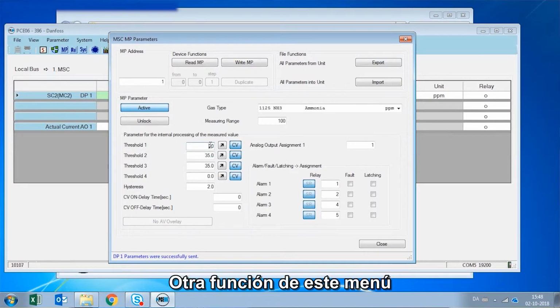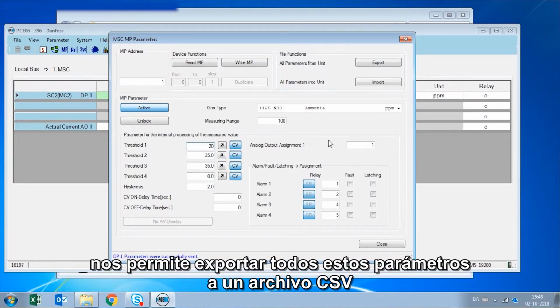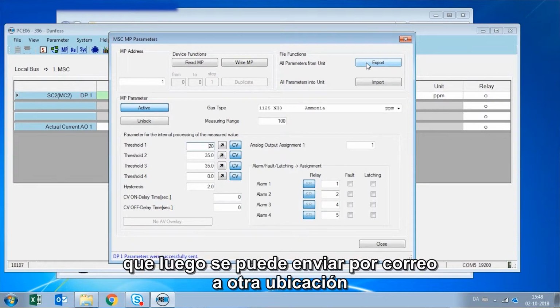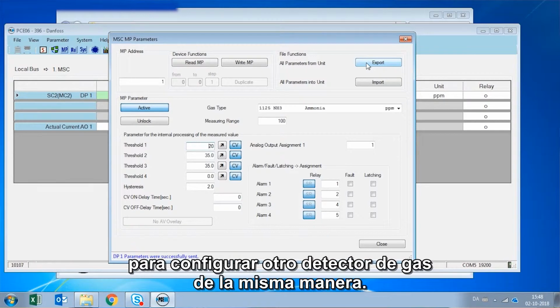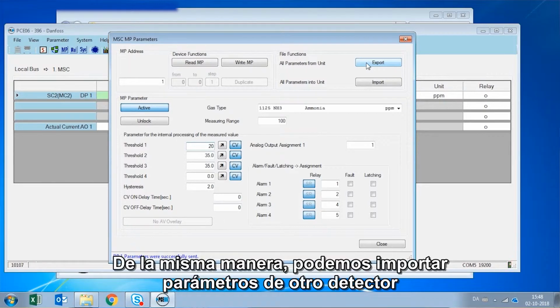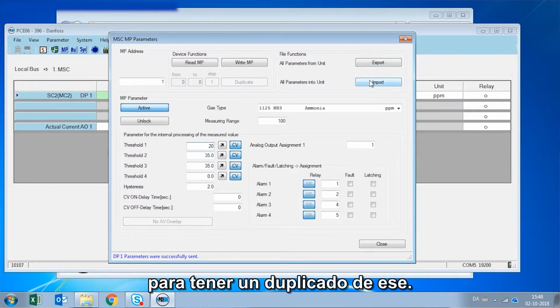Another function of this menu is that we can export all these parameters into a CSV file that can then be sent by mail to a different location for another digital gas detector to be set up exactly the same way. And by the same means, we can import parameters from another digital gas detector to have a duplicate of that one. So we're going to move to the next menu, which is the relays.